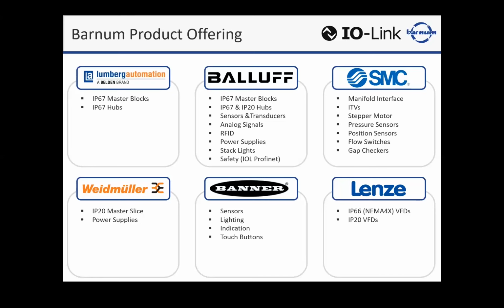So now with Lenze's offering, they have a great IP65 drive at a very nice price point that you can go and decentralize, control your motors, and not only start, stop, forward, reverse, monitor faults, see 100 parameters of what's going on with current, torque, anything that's going on with that VFD. So that really is going to change the game, because now we're going to be able to put VFDs, say, along a conveyor, decentralize where they need to go, plug and play, network or IO-Link connection via a standard prox cord, and you're doing all your motion control.